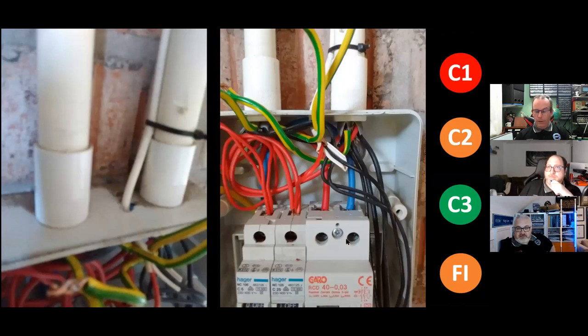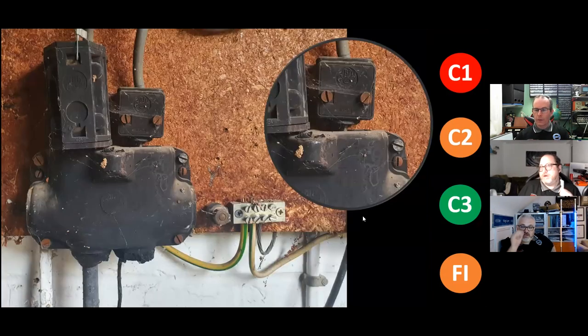So straight away looking at that, obviously it had a board cover on, by the way, so all you saw was a cable tie up to the top, but that to me was a C3 at first look. But the mixing and matching, the doubling up on the breakers, the 25 amp on them cables, I think they're 2.5s, C25s, push that towards C2. Looks like the majority of guys have. We've got 35% C2. Great.